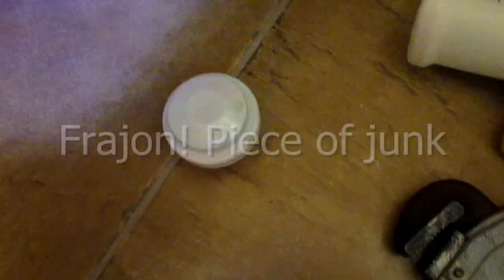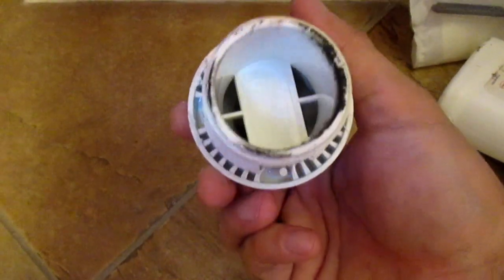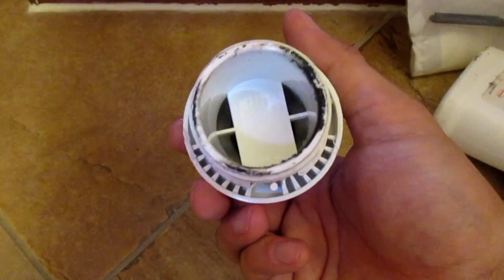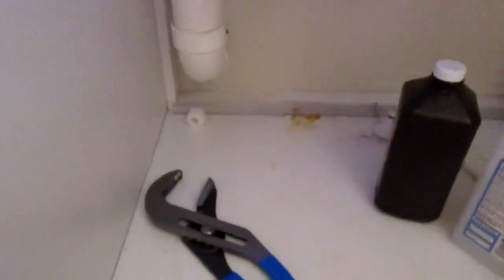It's backing up sewer gases. This was actually made in Naples, Florida — just south of here. Beautiful Naples, with the most millionaires that show up for two months out of the year. I don't think there's anything fancy about it. They have all red tied all the way up here. There's a one-way valve on it — it should let air in but it shouldn't let air out. This valve is so cheap and hardened, I don't even think it worked. There's a nasty gas smell coming out of this pipe.